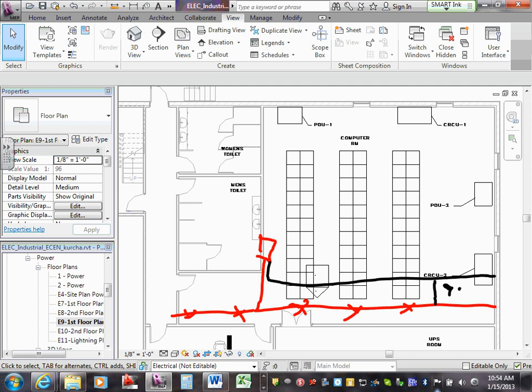Did that confuse everybody? What they're trying to avoid is you have millions of dollars of servers crunching transactions for people. You really don't want somebody sleeping in the room to knock off one of these sprinklers and give him a shower. That's what they're trying to avoid here by having this air. So if you accidentally knock it, you just vent air out of it, then somebody else will go there, and no water is going to come down and damage the equipment.